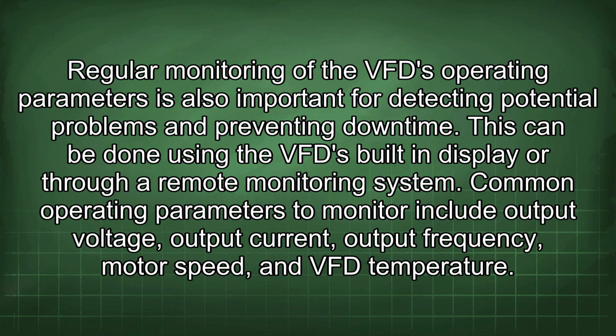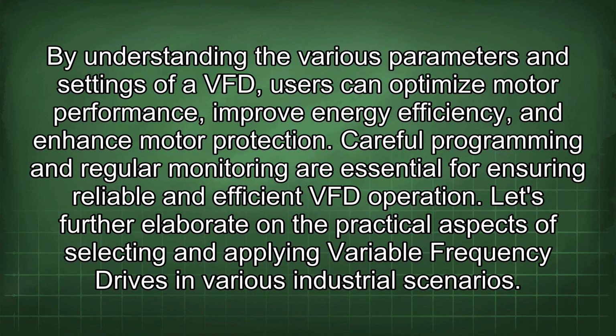Regular monitoring of the VFD operating parameters is also important for detecting potential problems and preventing downtime. This can be done using the VFD built-in display or through a remote monitoring system. Common operating parameters to monitor include output voltage, output current, output frequency, motor speed, and VFD temperature. By understanding the various parameters and settings of a VFD, users can optimize motor performance, improve energy efficiency, and enhance motor protection. Careful programming and regular monitoring are essential for ensuring reliable and efficient VFD operation.